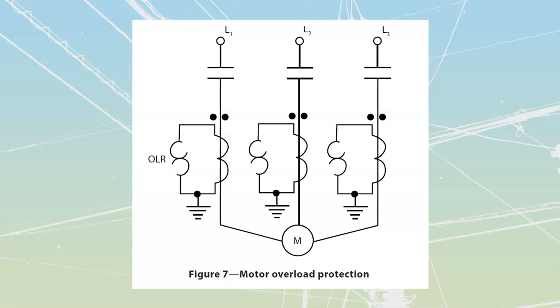If I have a 1,000 horse motor—yes, motors that size do exist—those motors will have a gigantic amount of current running into them, and we would not want to place in overload heaters. You should remember what an overload heater is from your second year motor control: it's literally something designed to dissipate heat. The more current that travels through this overload heater, the more heat it dissipates.